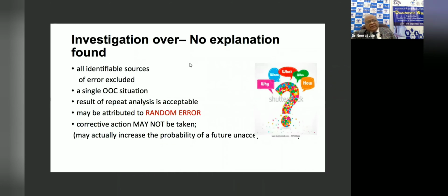Now you have checked all these things. Still, what happens sometimes? You're not able to find anything. Then it may be considered as random error, some voltage fluctuation. So then you can classify that as random error, and you are running control again. And if that control result is within acceptable limit without any corrective action, then this may be classified as random error. But if you are getting this random error very frequently, that means there is some problem in your root cause analysis.